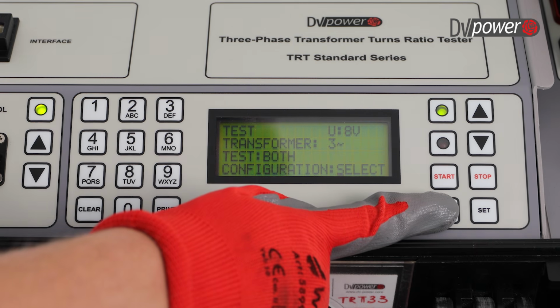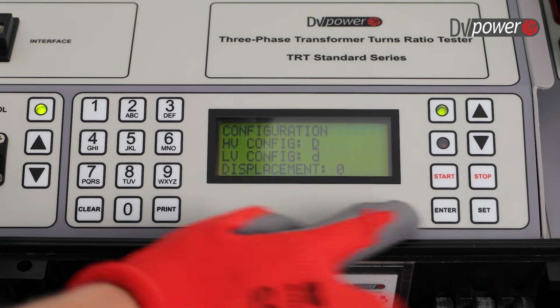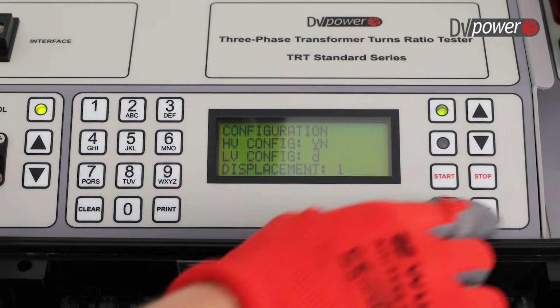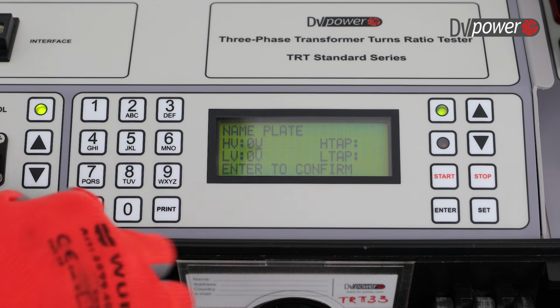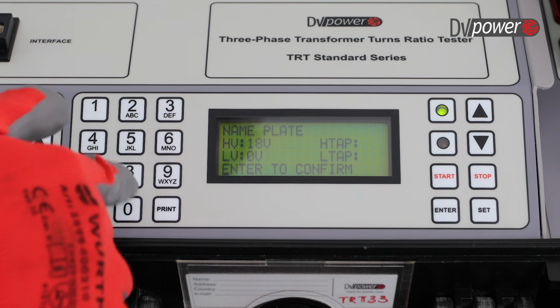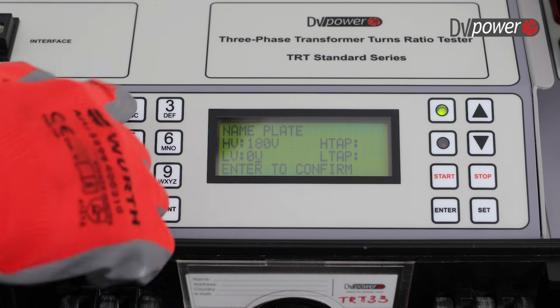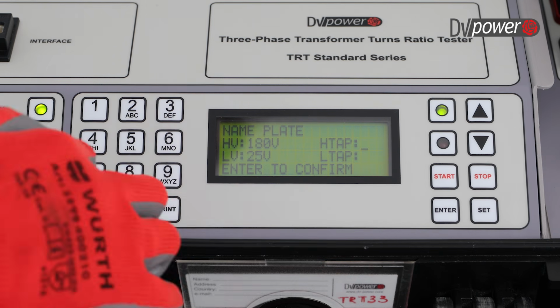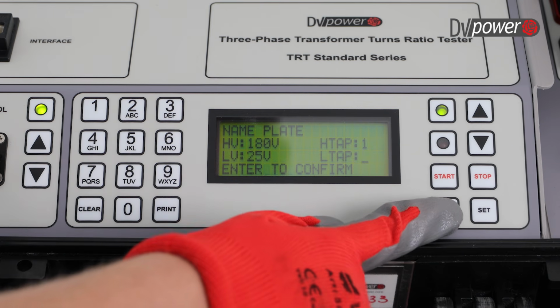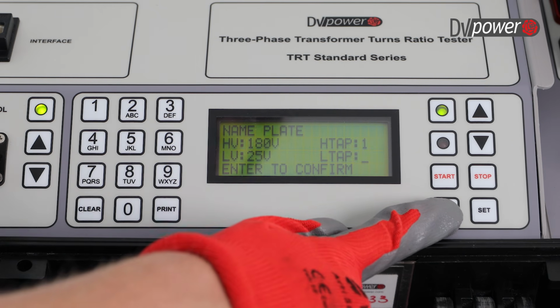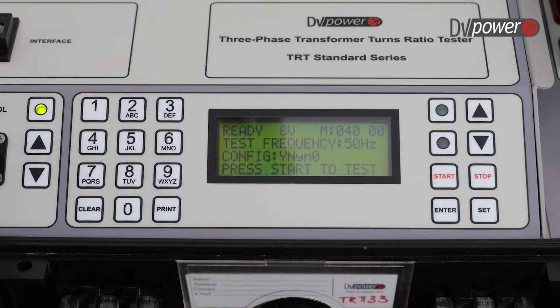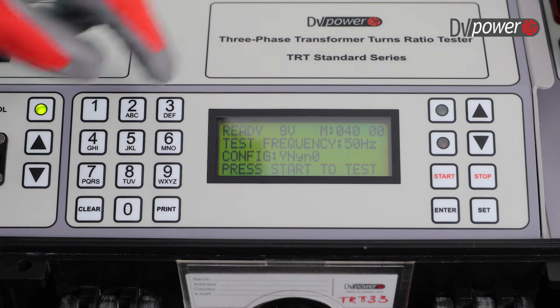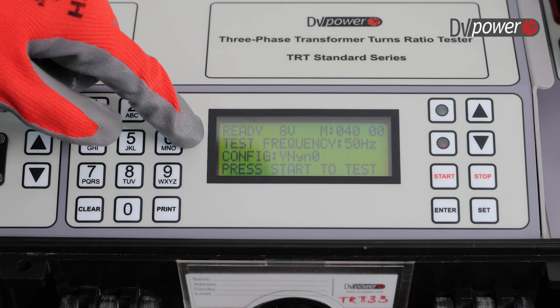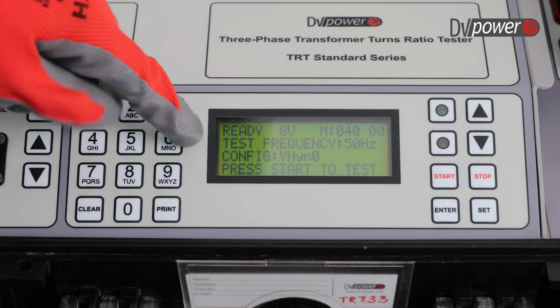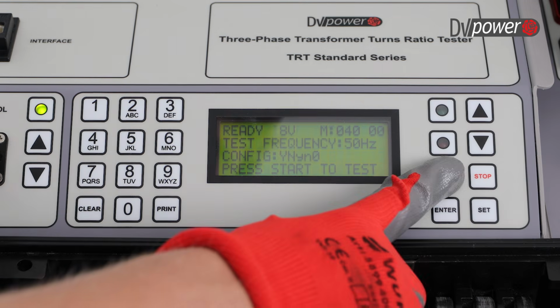Press enter, and we will manually select the vector group. Vector group is YNyn0, and we enter the nameplate, which is 180 to 25. We test the first tap. There is no taps on a low voltage side, and we press enter to continue. Memory location is shown. It's number 40, 50 Hertz. This is something device recognized from the grid configuration, and we press start to test.